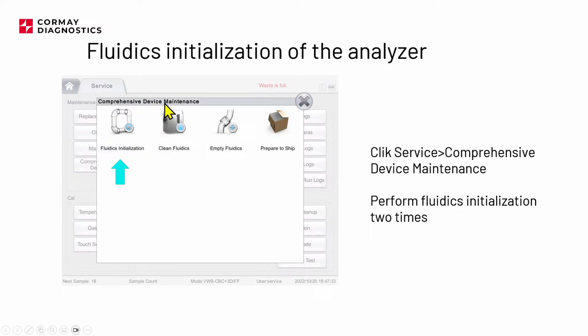make a fluidic initialization. Just go to the comprehensive device maintenance. It's in the service menu, and make the fluidic initialization, let's say 2 times, because this is also priming the reagent. It is removing some air bubbles and preparing your device for future use.